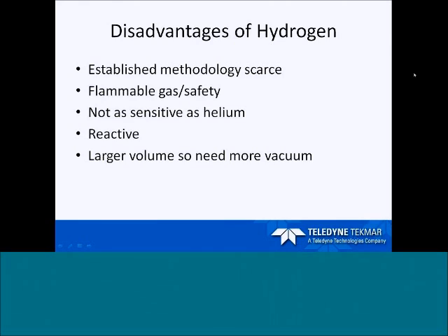It's also a reactive gas, unlike helium. And because of that, you'll see later on there's some problems with tuning and other things. And since you need a larger volume of hydrogen on your column, you're going to need more vacuum.